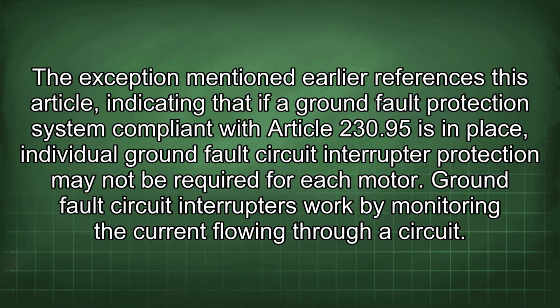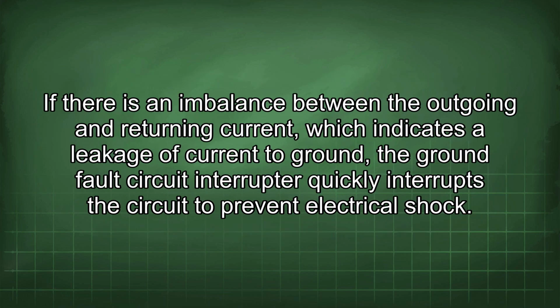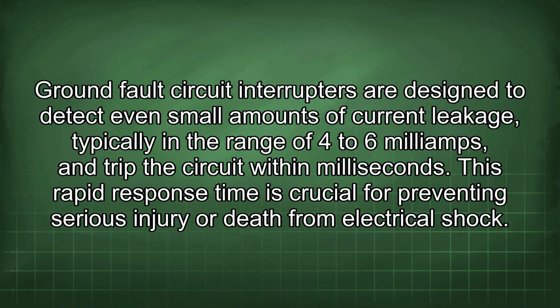Ground fault circuit interrupters work by monitoring the current flowing through a circuit. If there is an imbalance between the outgoing and returning current, which indicates a leakage of current to ground, the ground fault circuit interrupter quickly interrupts the circuit to prevent electrical shock. Ground fault circuit interrupters are designed to detect even small amounts of current leakage, typically in the range of 4 to 6 milliamps, and trip the circuit within milliseconds. This rapid response time is crucial for preventing serious injury or death from electrical shock.